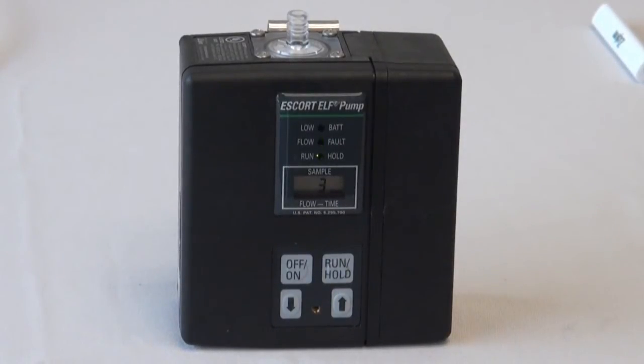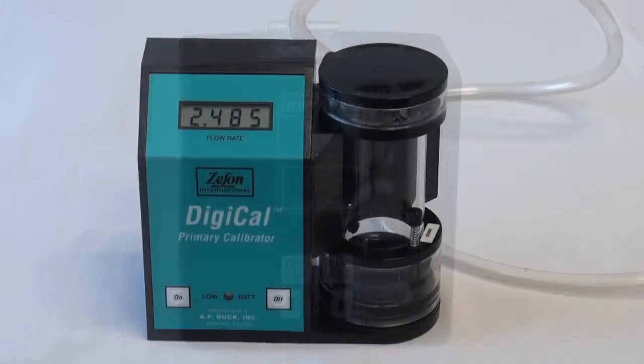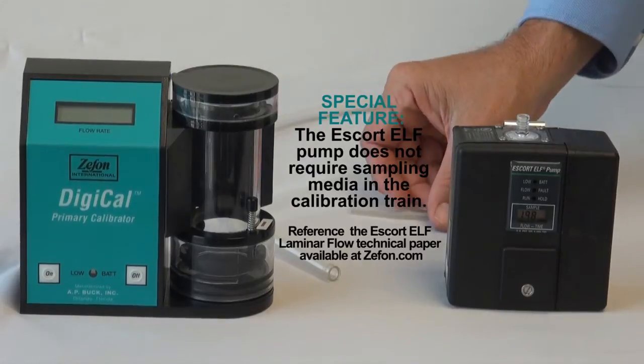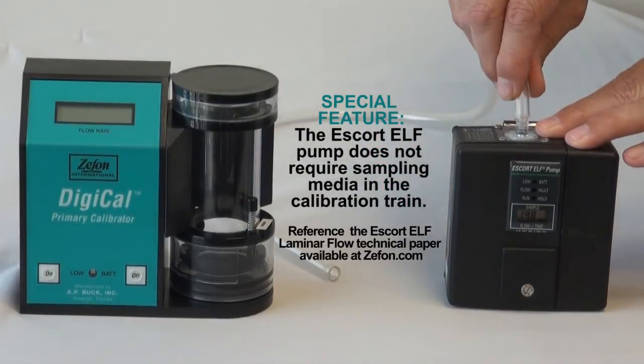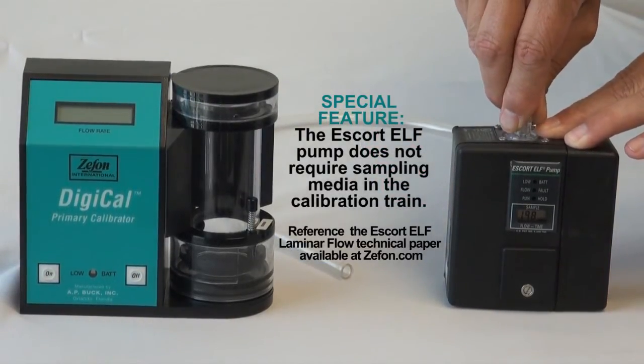Leave the pump at 2.5 liters per minute and turn the pump off. For our demonstration, we will be using the Zefon Digi-Cal 5 as our primary standard calibrator. Connect one end of the tubing to the Escort pump, then connect the other end to the primary calibrator.